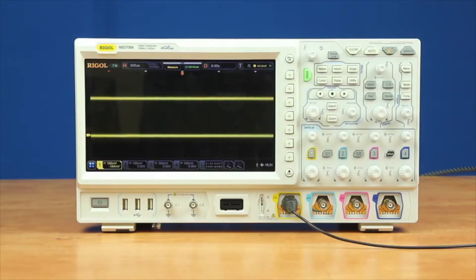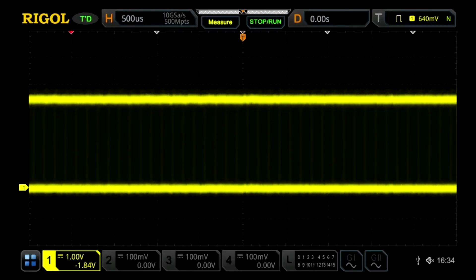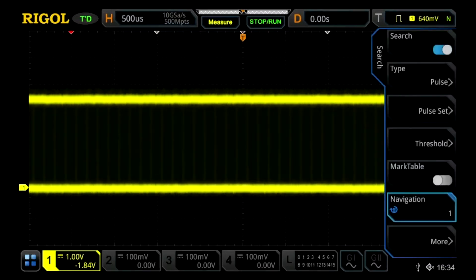Looking at the same signal on the Rigol, the additional memory depth gives us a higher sample rate and more signal fidelity. We can use the same trigger type and search type looking at a pulse width.